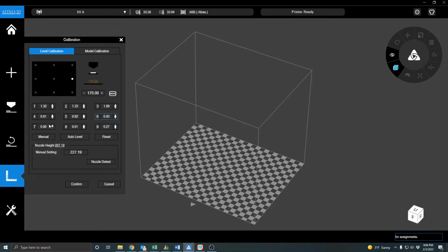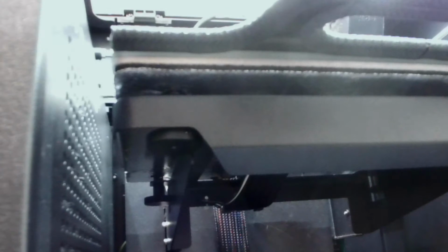So what this tells us is that we are sloped too far to the back, and these values are outside of that 0.5, or at minimum 1.0, but the best or optimal range is up to 0.5. So now we're going to go through our process to do some manual leveling to fix this issue. So I'm going to switch to a different view. We're going to go to our webcam.